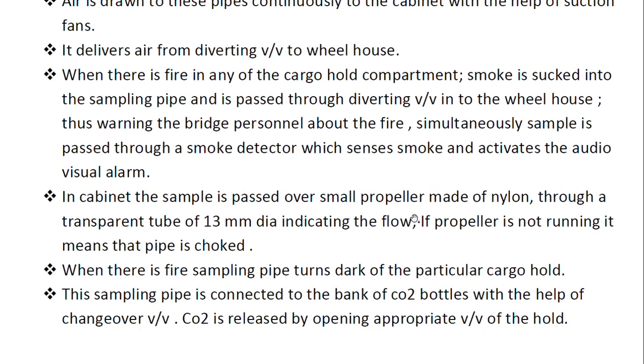Inside the cabinet, the sample is passed through a small propeller made of nylon, through a transparent tube of 13 mm diameter — this tube serves as an indication. When there is a dirty or smoky sample, the tube will turn black or change color. If the propeller is not running, it indicates the pipe is choked. When there is a fire, the sampling pipe of the particular cargo hold turns dark — since there is a separate sampling pipe for each cargo hold, the affected unit can be identified.